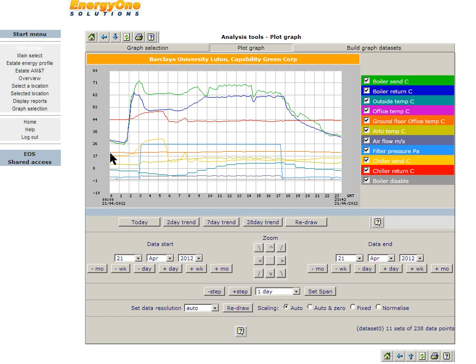A good performance. However, this graph shows the plant activity starting at midnight up to the current time. It can be clearly shown that at midnight, the boiler flow and return were slowly dropping, as could be expected from the previous day's activities. However, at around 2 a.m., the boiler came on, possibly as a result of some faulty setting in the main building management system or as a result of a temperature variance setting in the BMS. The flow and return climbed quickly, showing that there was very little, if any, demand.